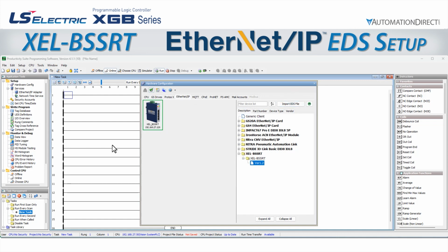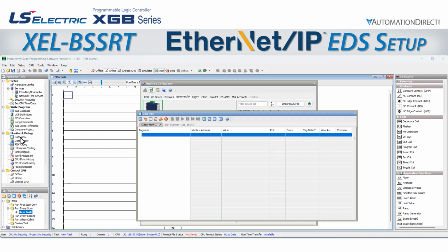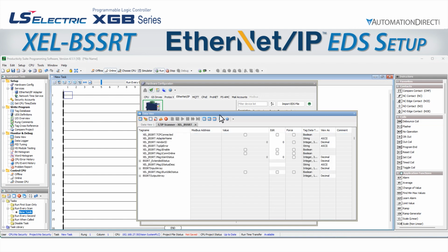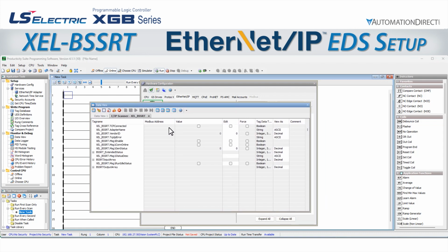If we now double-click Data View on the left side of the screen, it will open our data view, and our second tab is the BSSRT information. None of the information is populated yet because we haven't initiated the connection. Let's enable the message by checking the box next to MSG1 Enable, and then send that edit to the CPU. We get the TCPConnected return. The software populates the adapter name and vendor ID, and the connection online Boolean also becomes true.